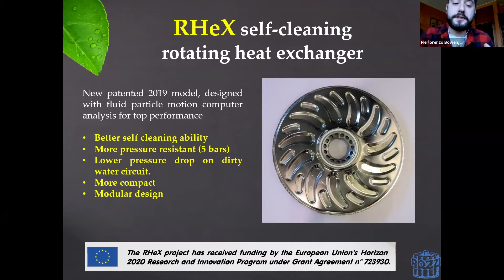Now, what I mean by modular design is that the rotor itself used to be welded together, and now it's in a gasketed system. This means that we are able not only to, in case it were required, change a single disc instead of a full rotor, but also because we don't need space for welding anymore, we can put the discs closer together. So a more compact and a more efficient unit.